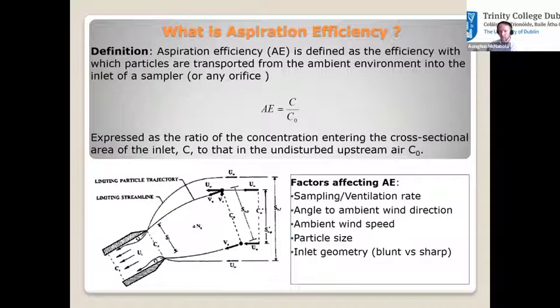But in fact it's actually quite difficult for that to be the same all the time, because there are a number of factors determining whether the particle enters the sampler or not. Unlike gases, particles have mass and inertia, and are driven by the ambient wind. There's also a balance of how much force we're applying through the suction or ventilation rate of the sampler.